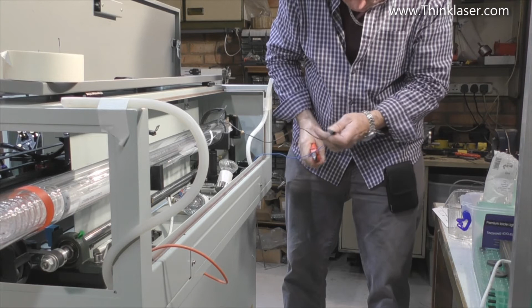Now this end doesn't have any high voltage on it at all. This is completely low voltage, and we've got a bullet connector on there which is perfectly okay. But if you don't have a bullet connector, once you've broken that, you might not be able to replace it. What you can do instead is use a screw connector, and that's what I'll do inside this piece of insulated sleeve.